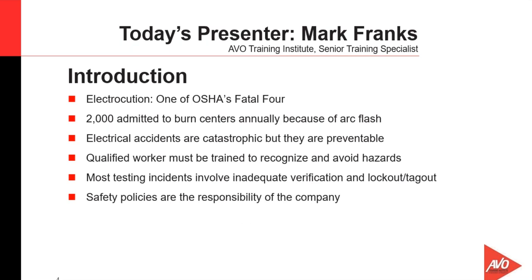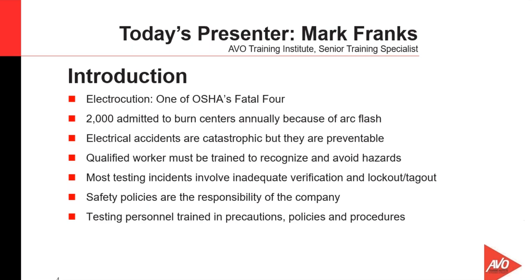That's one reason that training in recognizing and avoiding hazards and how to mitigate them is so important today. Most incidents involving testing, fault locating and cable testing actually involve inadequate verification of power and/or issues in lockout tagout.